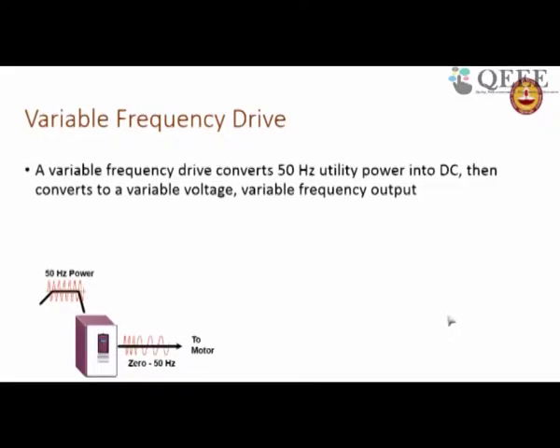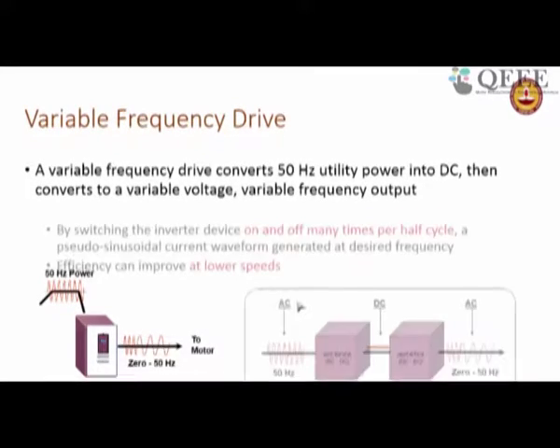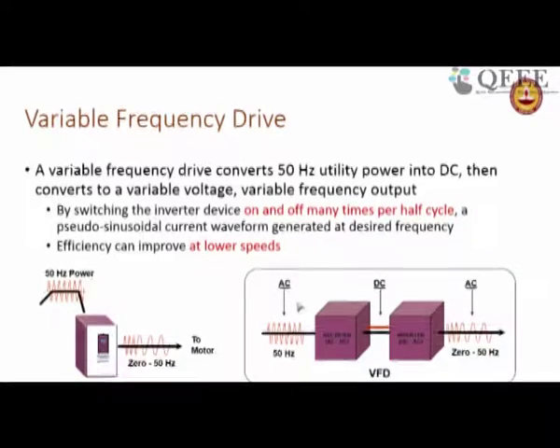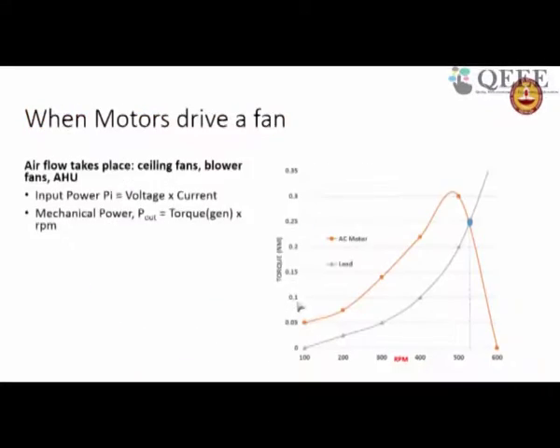Variable frequency drive: you take AC and convert it to variable frequency AC. Why? Because if you drive an induction motor, its speed depends on frequency, so to get a different speed you must change the frequency while still retaining efficiency. To do this, you first convert AC into DC, then convert DC back into the required waveform. Again, this is power electronics at work.